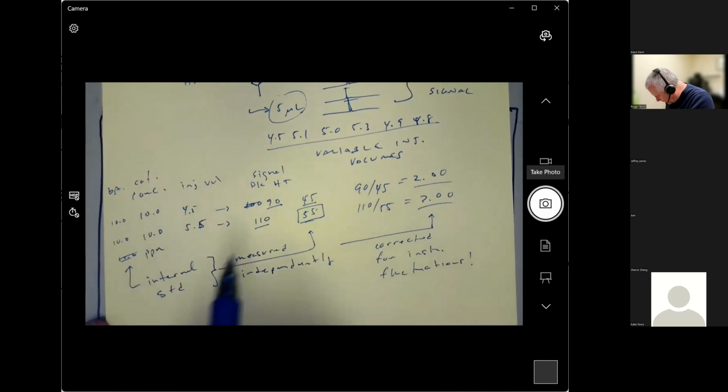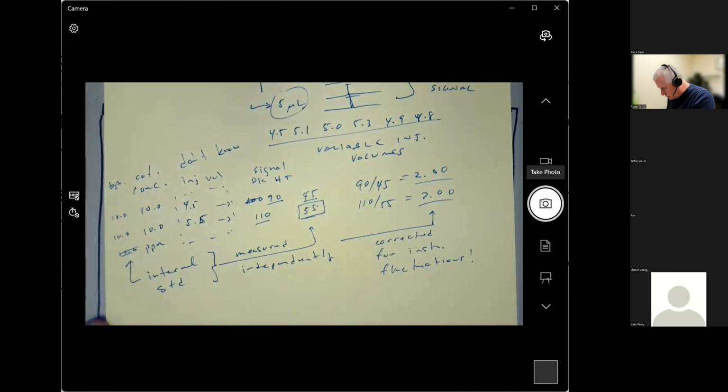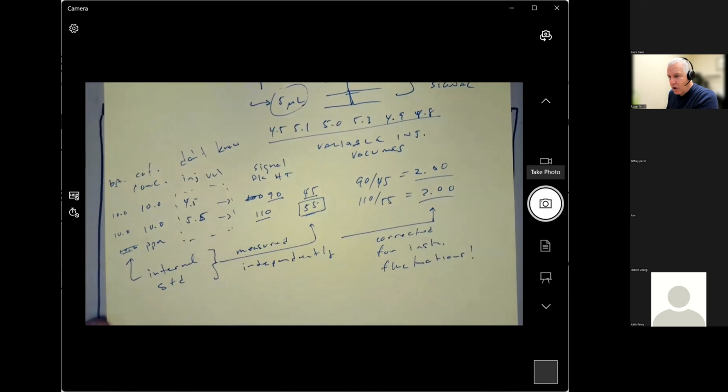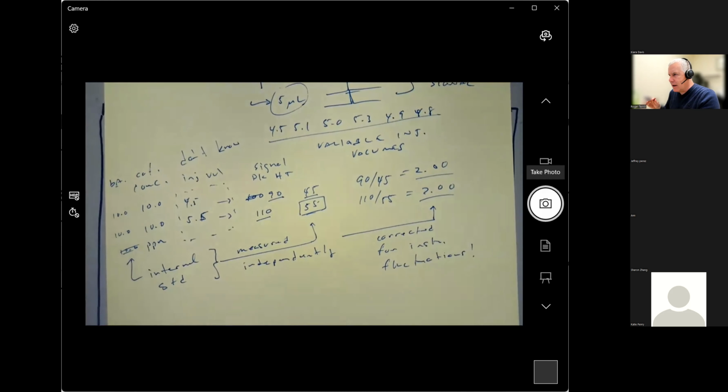And so the thing about it is that this is the part that we don't know about. We don't know how the injection volume is varying, right? This is hidden from us. I mean, we just don't know, right? Because it's a malfunction in the instrument, right? And it doesn't tell us, oh, I under injected or I over injected. It says, I tried my best, right? I don't know how much went in, right?